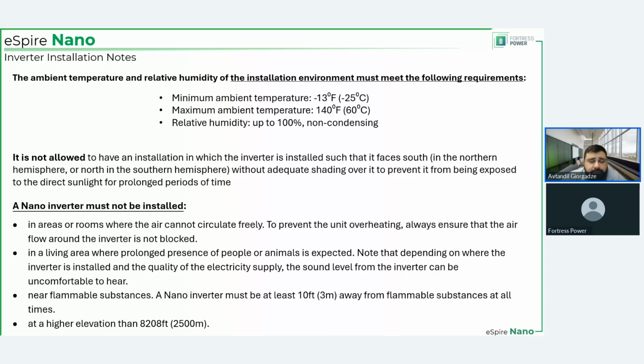And although the wording here suggests that the system must not be installed at a higher elevation than 8,208 feet, that is not quite true, is it now? Because we can derate the inverter, and then you can have it at higher elevations. It's just that at this elevation, we need to start considering derating the inverter. Again, that depends on your usage pattern, right? Because usually my approach is, let's deploy the system, let's monitor it, especially if it's like a new development or something like that, and we have no idea how much power will be used and at what rate, for how long, that type of thing. Let's monitor the system.